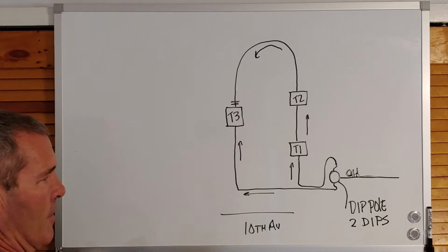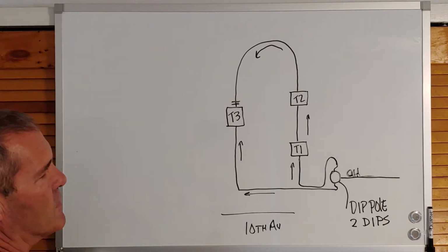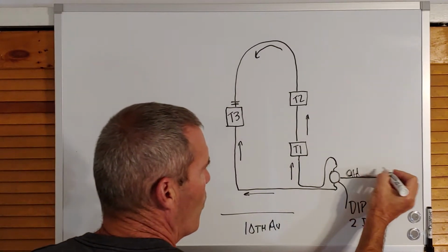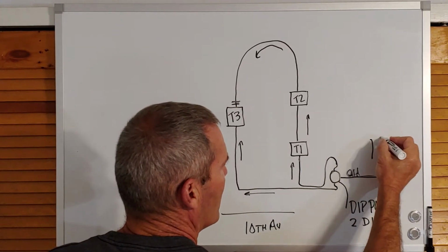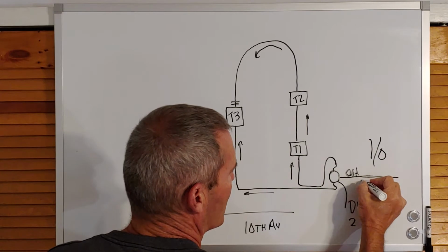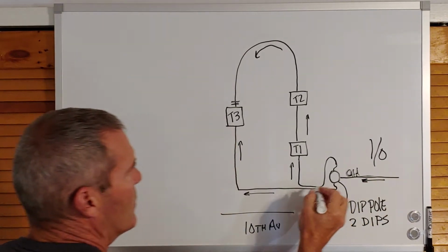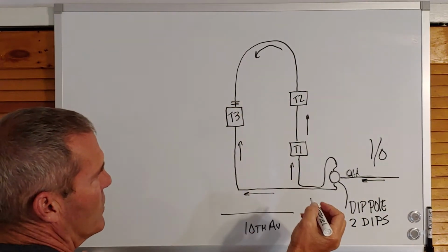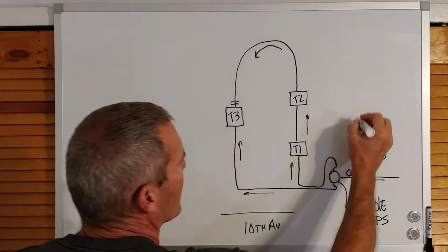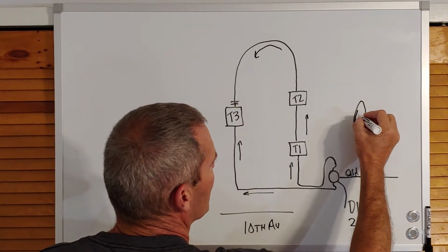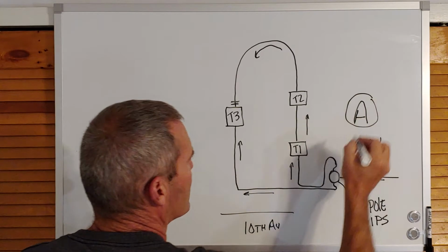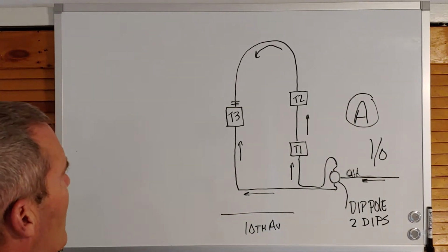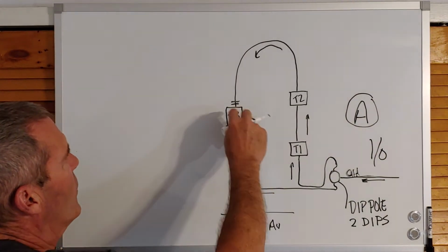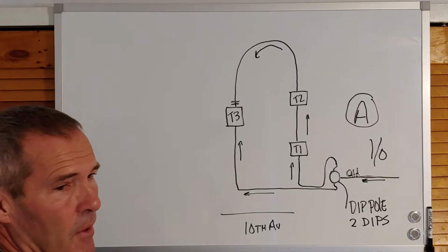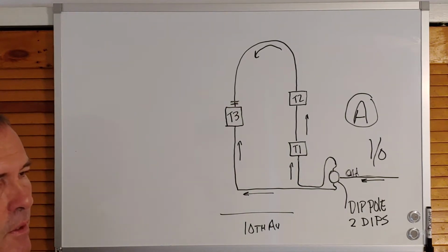Now keep in mind, and this is why I want to keep this one simplistic, I'm using 1 phase of primary overhead coming in, so I know my phases are going to match. We'll say, just for goodness sake, it's A phase. So we know our normal open point is this direction, and I'm going to go through two different methods, both the underground fault indicator method and the high pot method, to show you what you're going to do actually out there in the field when you come up.